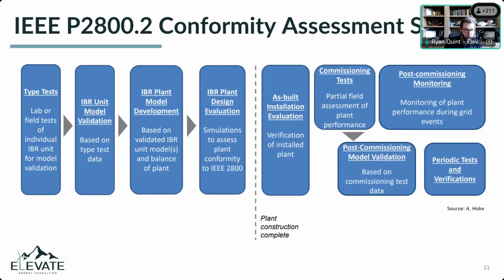What I want to focus on is a slide from Jens's presentation that Andy often shares, showing the steps in the .2 conformity assessment process. It starts with OEM unit-level type testing and unit-level model validation, to make sure the model is reflective of the actual equipment, the inverter or turbine. Then we take that verified, validated information, model, documentation, and type test materials, and build a plant model representative of the project. We verify that, and use the plant model in our IBR Plant Design Evaluation, running simulations and verifications to make sure the plant meets the obligations of 2800.